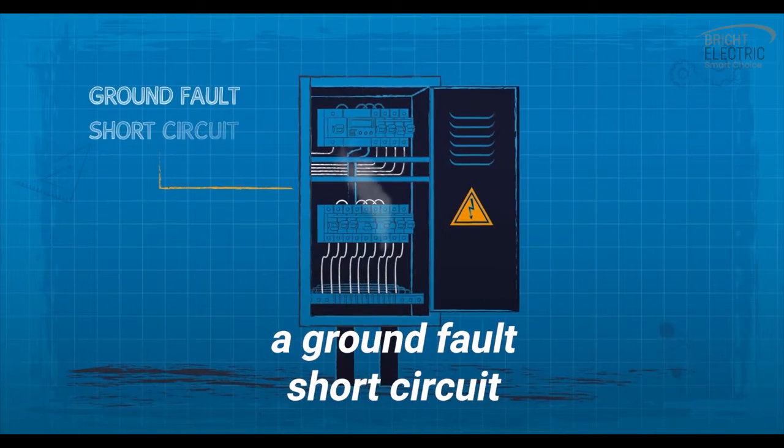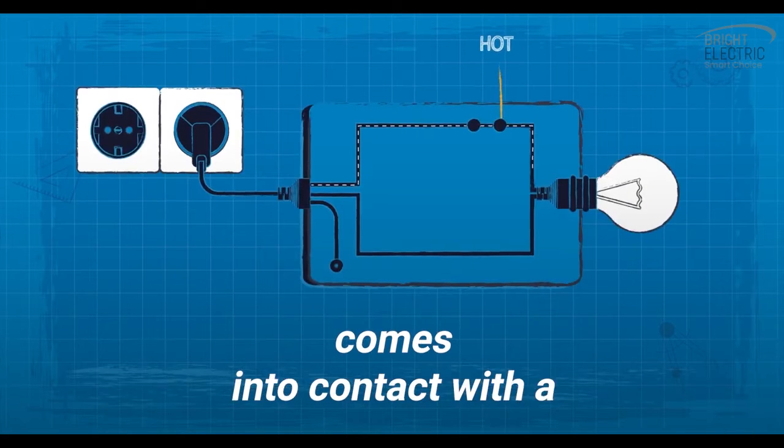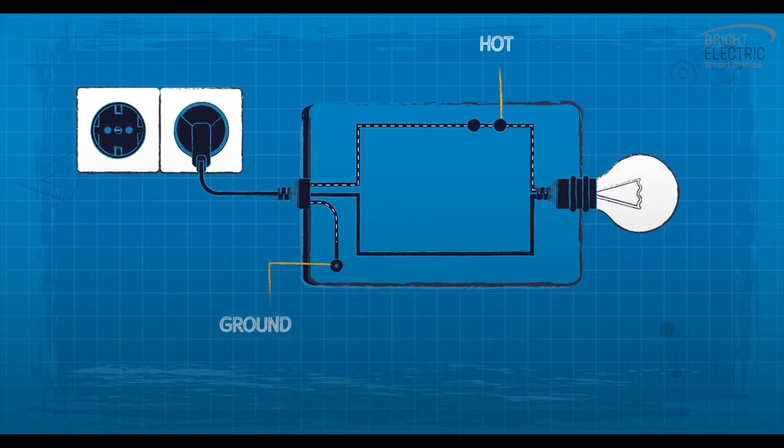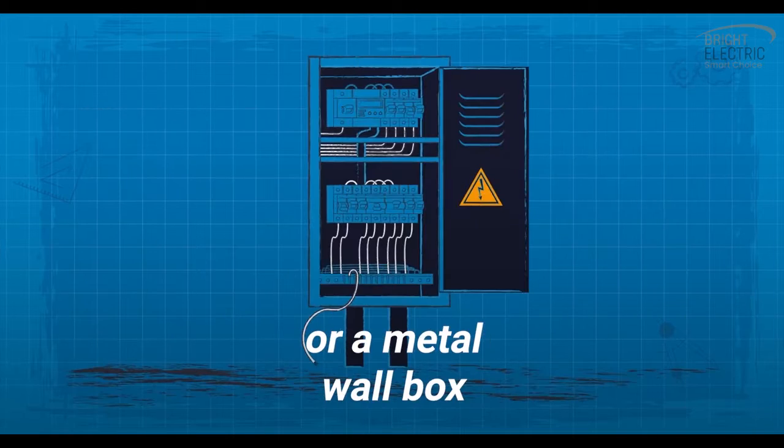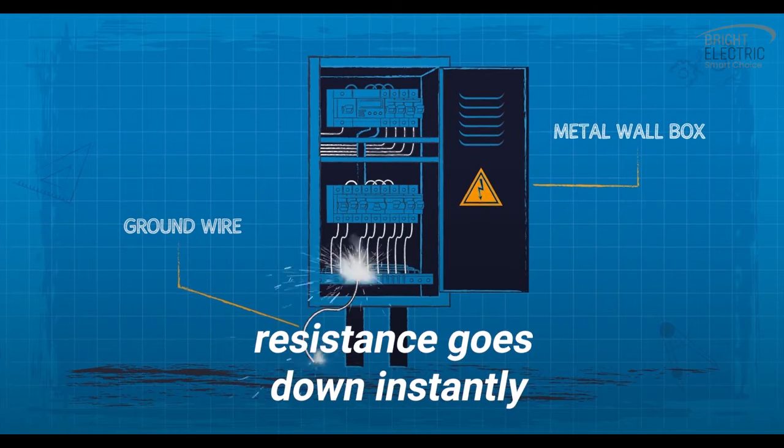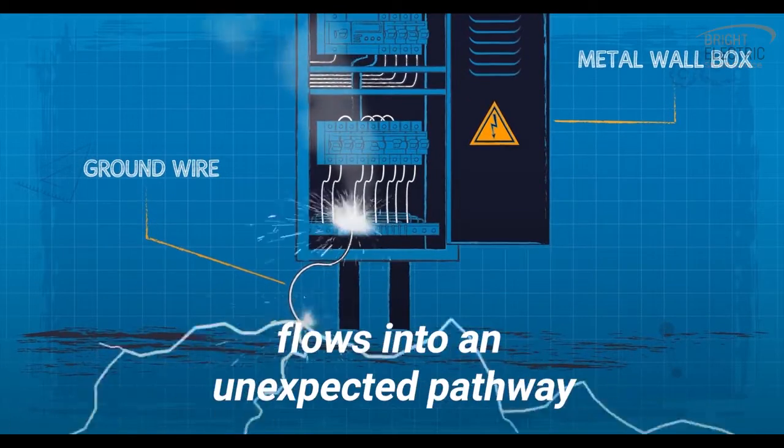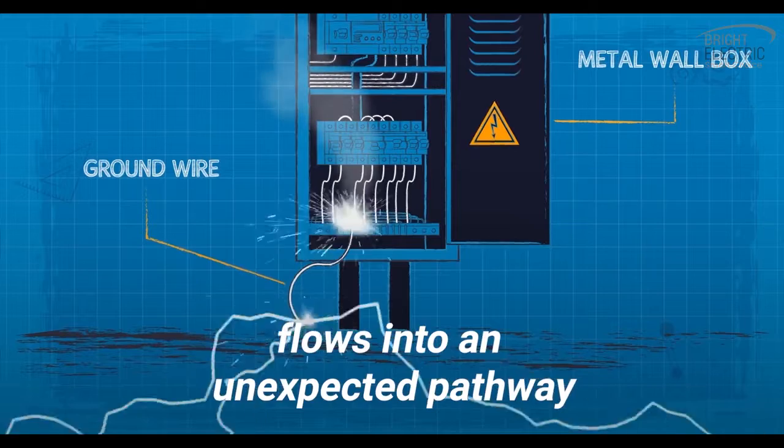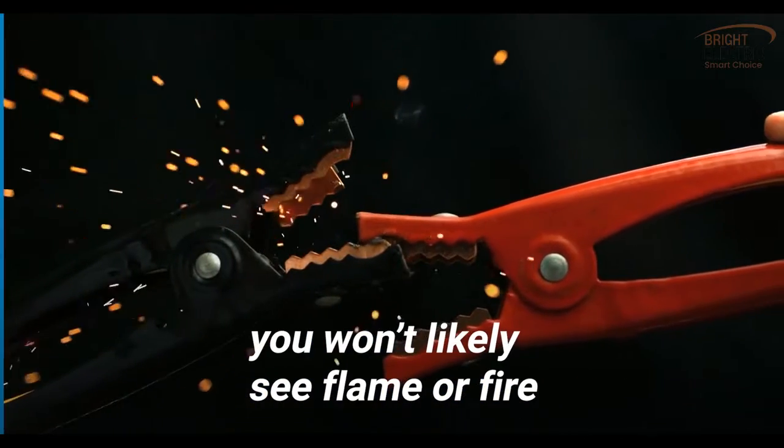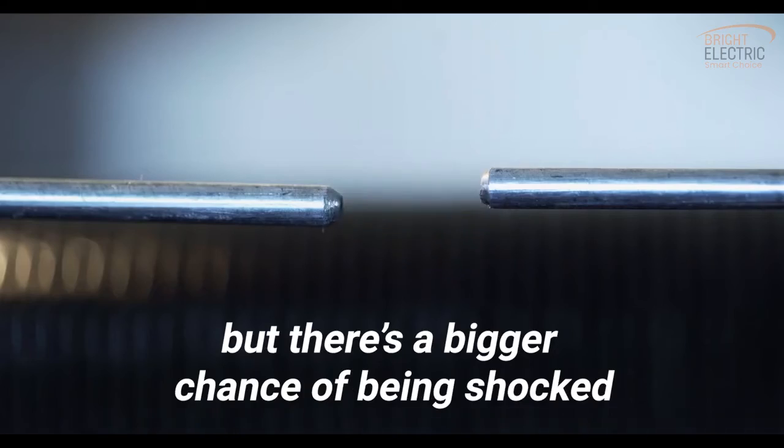The second type is called a ground fault short circuit, and it occurs when the hot wire comes into contact with a grounded portion of the system - for example, a bare ground wire or a metal wall box. Like a normal short circuit, resistance goes down instantly and a vast amount of current flows into an unexpected pathway. In this short circuit, you won't likely see flame or fire, but there's a bigger chance of being shocked.